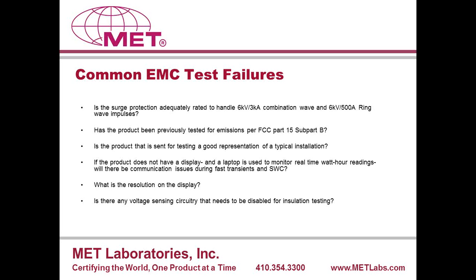The other thing to note is, what is the resolution on the display? Typically, when we are testing for any immunity test, that is what we are watching, to see that the display does not change by more than one least significant digit. Sometimes we have seen cases where the resolution on the display could be 4 or 5 digits, representing watt hours. Or sometimes a particular product has several digits being displayed, maybe up to 8 digits, with up to 5 digits, then a decimal point and 3 digits after that, which comprises your display resolution.